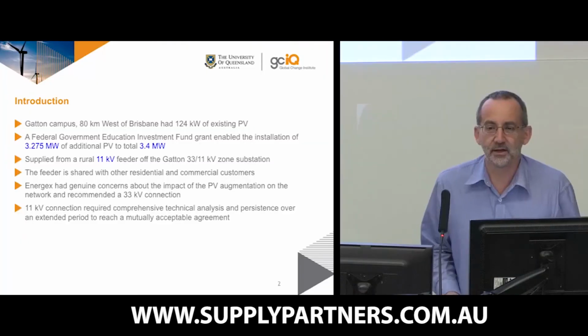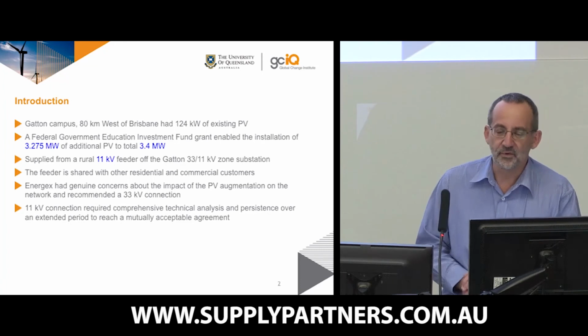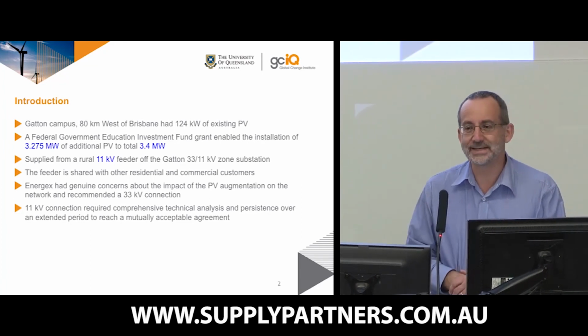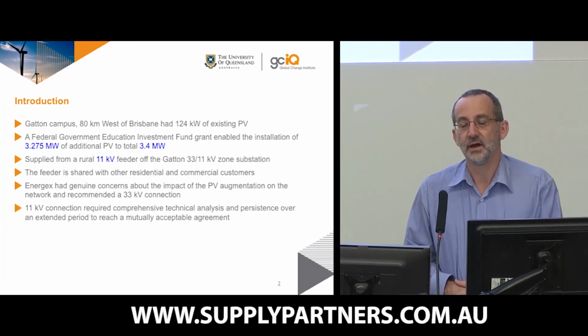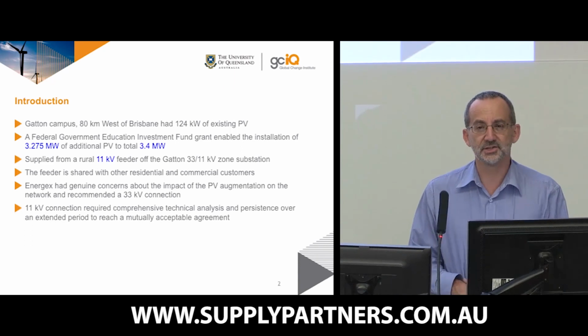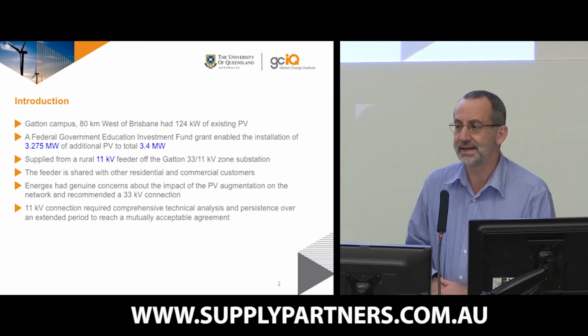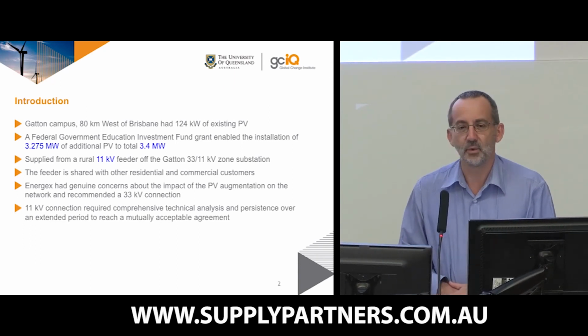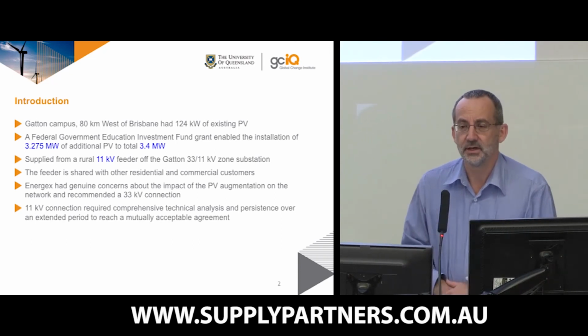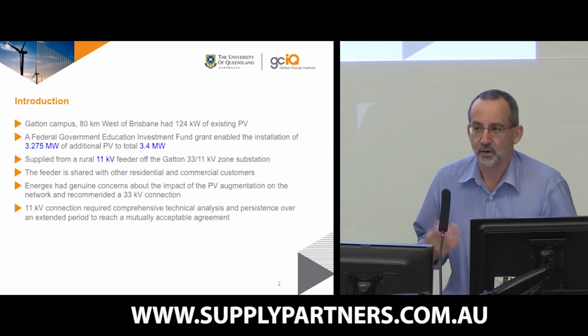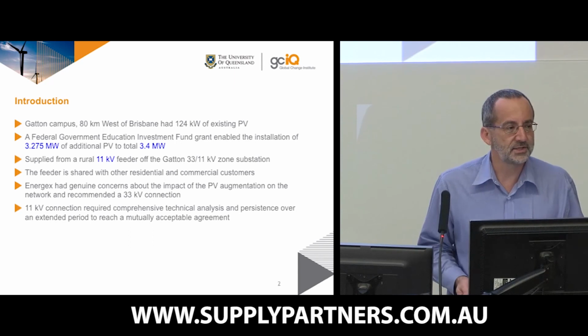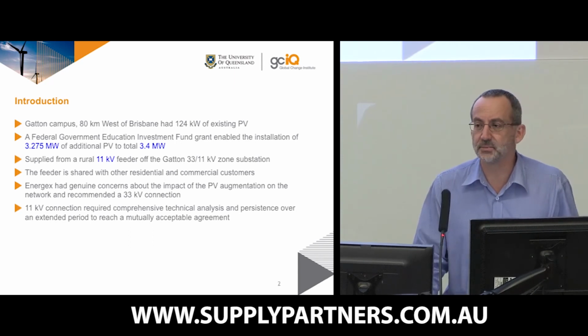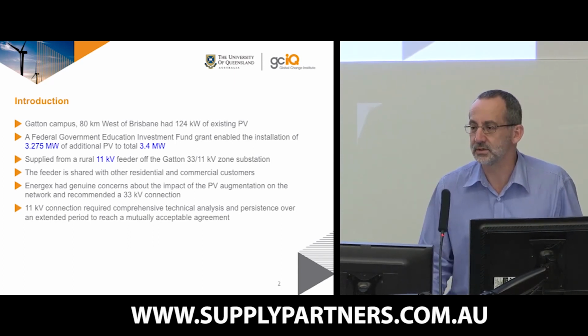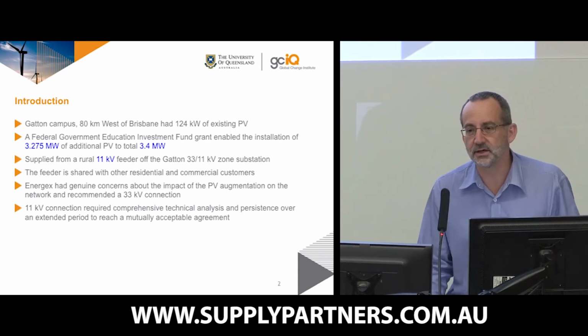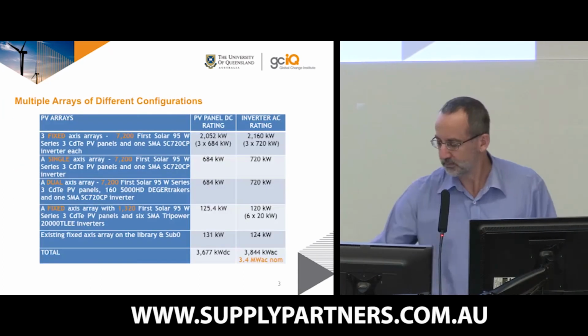Gatton campus is 80 kilometres west of here. We've recently put in 3.3 megawatts, connected on the 11 kV grid. That was one of the big issues for us - Energex were a little uncomfortable with connecting at 11 kV, they wanted a 33 kV connection. I'm well aware many of you have faced enormous challenges getting connections for small systems - I can tell you it was quite a big challenge to get a connection at 3.3 megawatts.